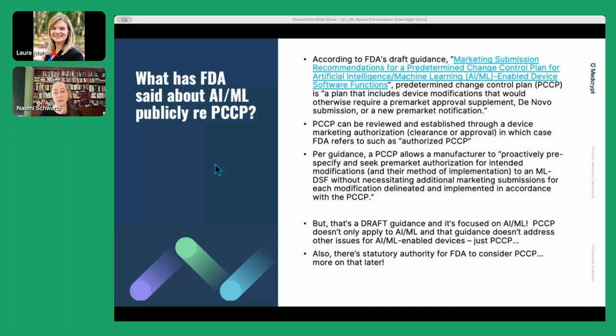But if you submit one of those types of pre-market submissions to FDA, with AI or machine learning enabled functions, and you include a predetermined change control plan, FDA has to review it now. They can review it and establish through the device marketing authorization, through a clearance or approval, or a de novo granting. And if they do that, the PCCP itself becomes referred to as an authorized predetermined change control plan.